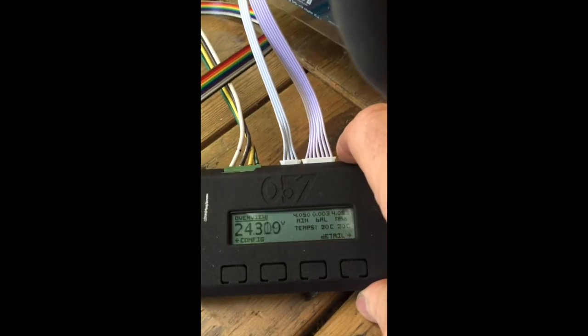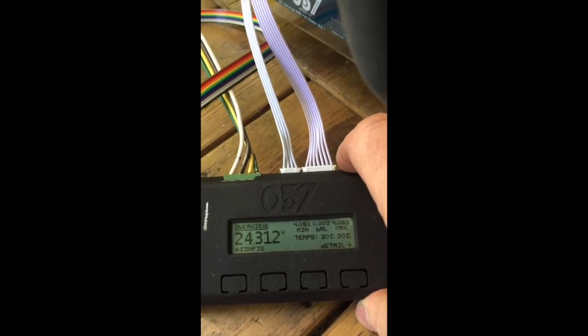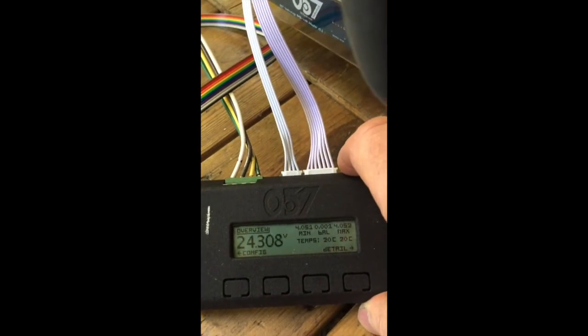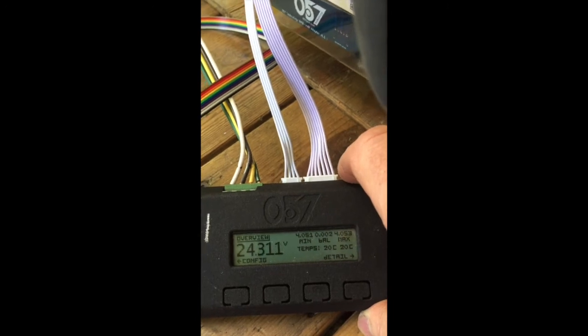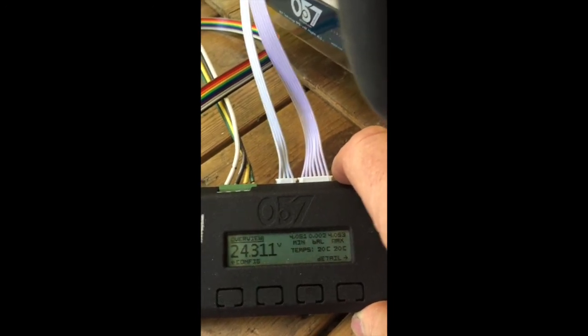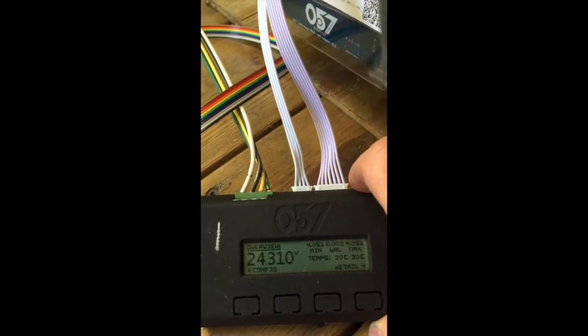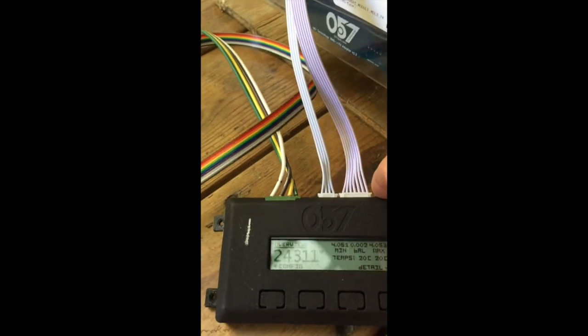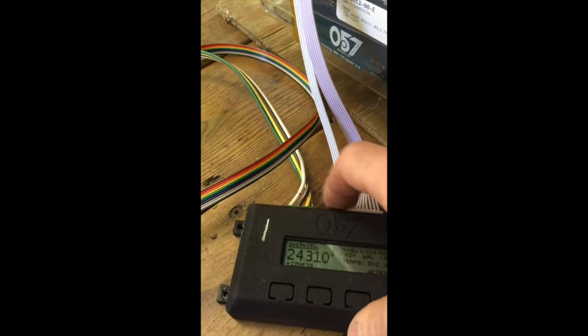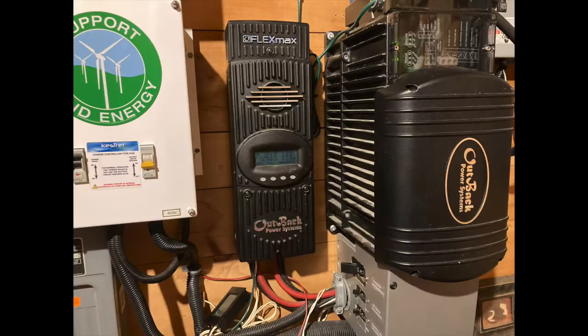057 sells what they call a mini BMS that's compatible with these modules. What it does is sense the battery voltage and temperature, and it allows you to program set points where you want some external action to occur. For example, if the battery voltage is too high, you want to shut off the charging source. Equipment in this system is designed to work well with lead-acid batteries. The solar charge controller manages reasonably well with the lithium charge profile, but the inverter charger is stretched past its low voltage limit.